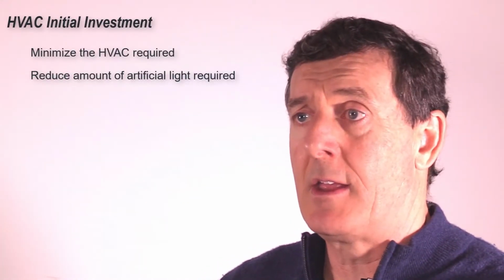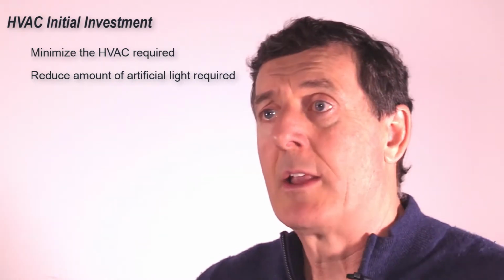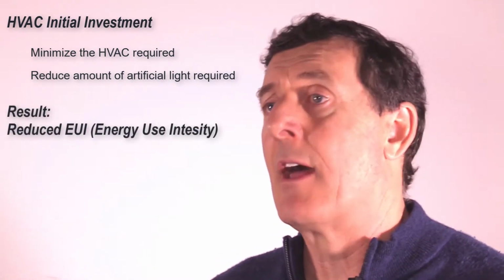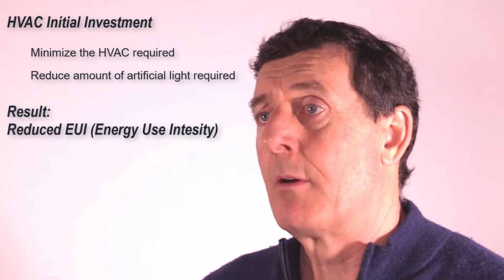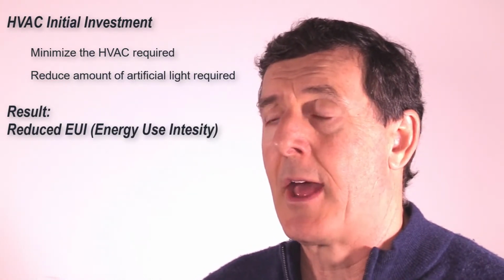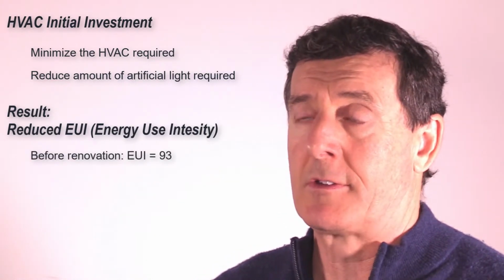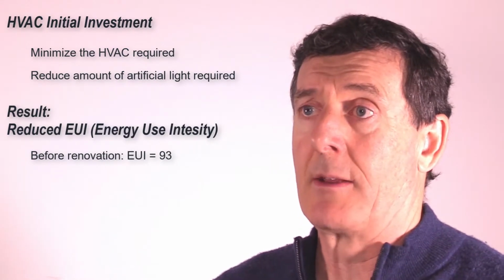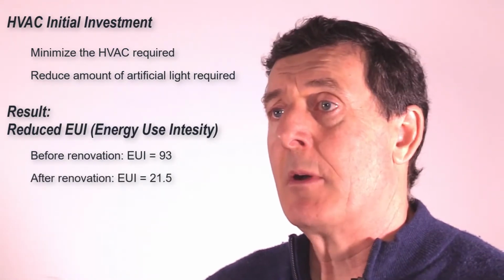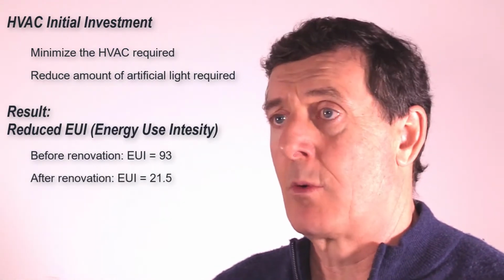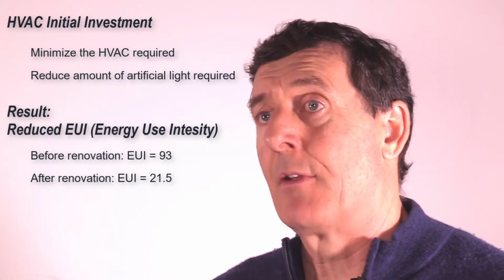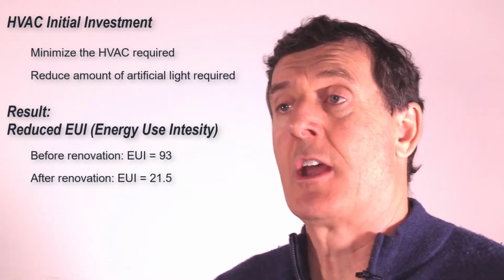That, combined with the reduced need for HVAC and air exchange, really drops the energy use intensity down significantly. This building, before we got involved with the renovation, had an EUI, or energy use intensity, of 93. We drove that down to 21.5, which effectively means we now need to generate about 25% of the energy to operate this building that we would have needed had we not done these improvements.